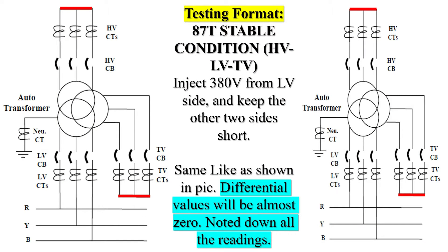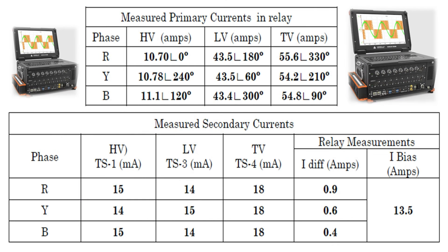There are several reasons that cause unwanted differential currents — for instance, alteration in the tap changer position, the features of loads, and transformer operating conditions. To make a differential relay as sensitive and stable as possible, restrained differential protection is developed for power transformers. The restrained current or bias current provides restrictions for the differential relay operation, stabilizing protection under fault conditions while still permitting the system to have good basic sensitivity.